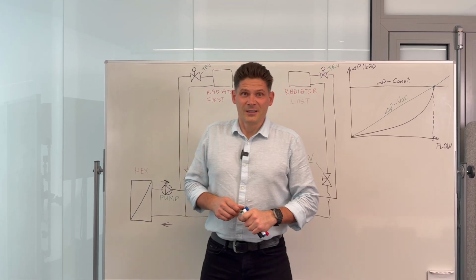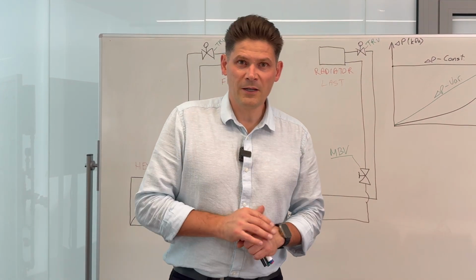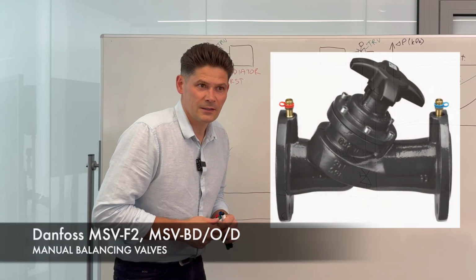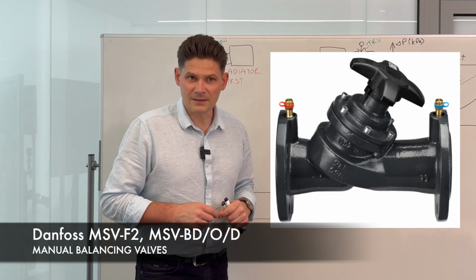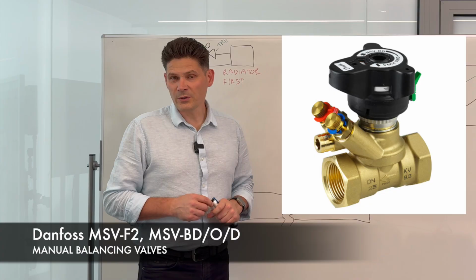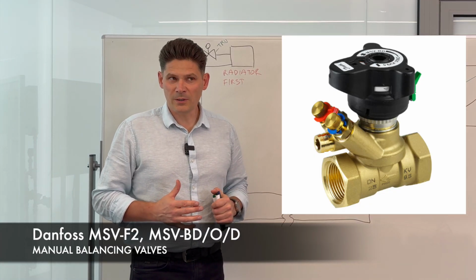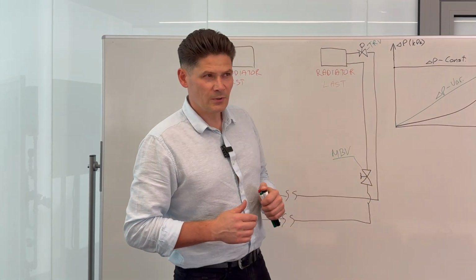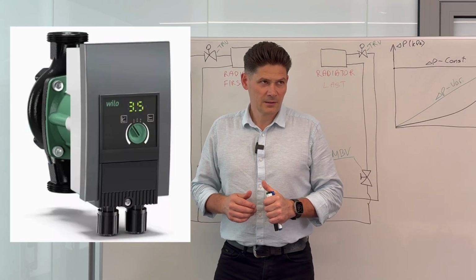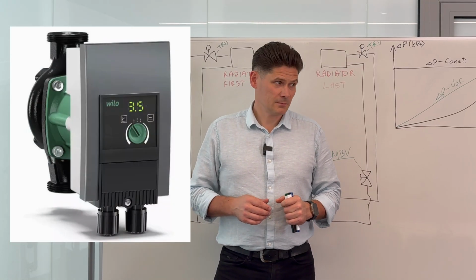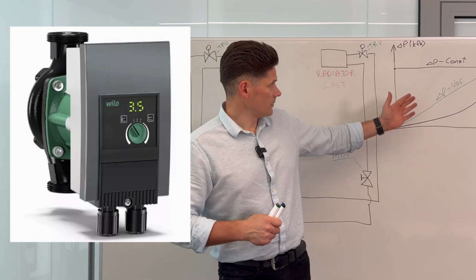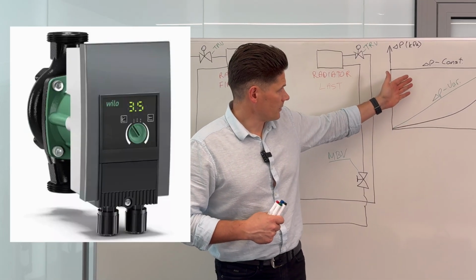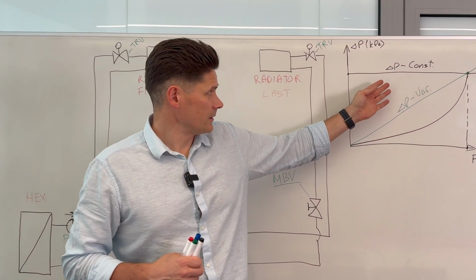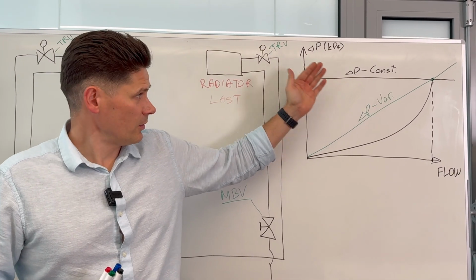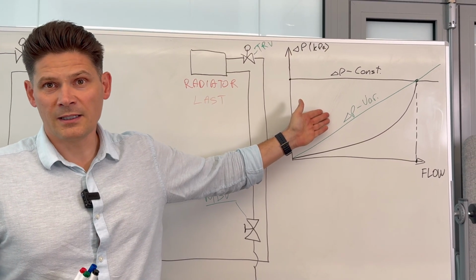Hello, let's talk about why manual balancing valves do not fit into our modern systems where we use electronic circulation pumps. In European Union, from 2013 we only have electronic circulation pumps, controlled either with constant delta P or with variable delta P.